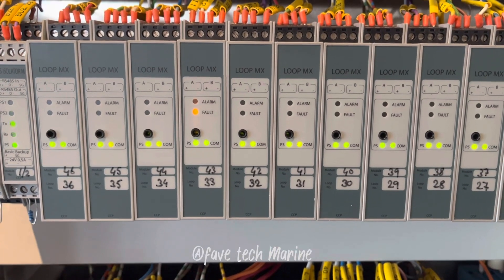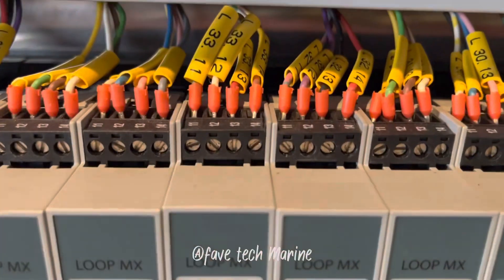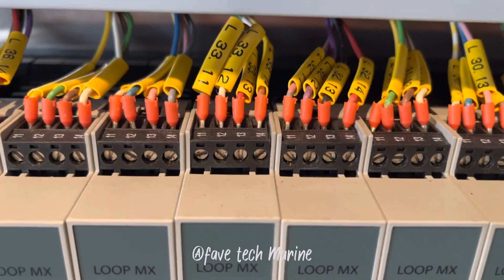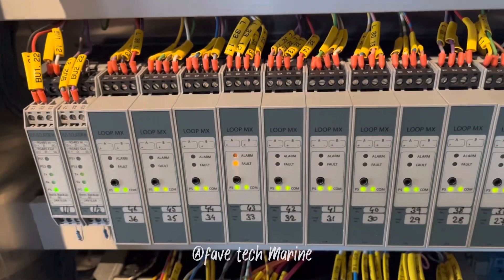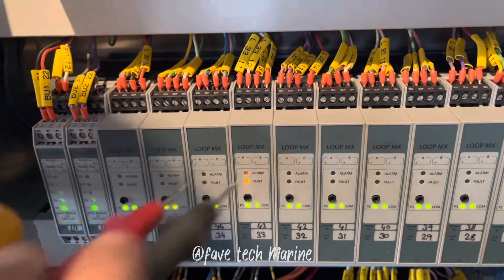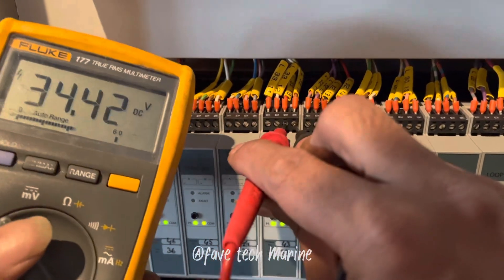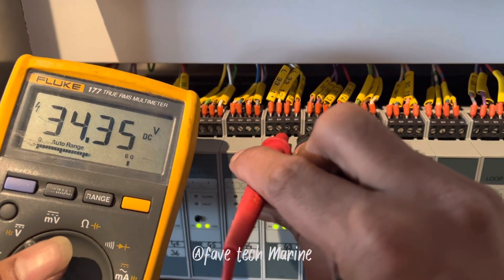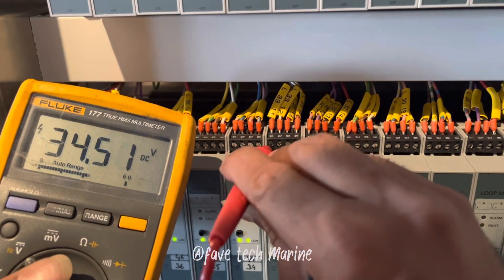Let's measure at the loop. Here you can find the fault — the individual lights are indicating here. The left side is the input and the right side is the output. I'm going to measure the voltage now — it's supposed to be 34V. The voltage will vary depending on the load. Let's measure the other end.